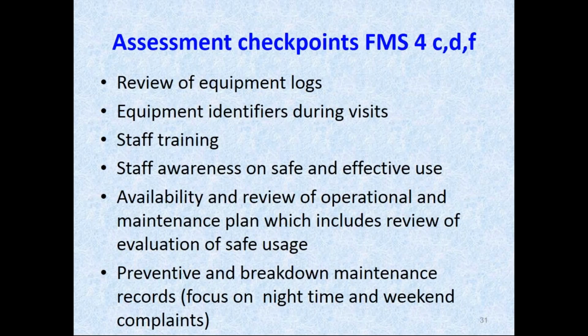Preventive and breakdown maintenance records should also be looked into, and look into the service reports, look into the breakdown reports, which you should focus on when you're on assessments. Look at complaints which have been raised at night times, look at complaints which have been raised on weekends, and check whether responses have been adequate, whether the complaint has been addressed and rectified as early as possible.